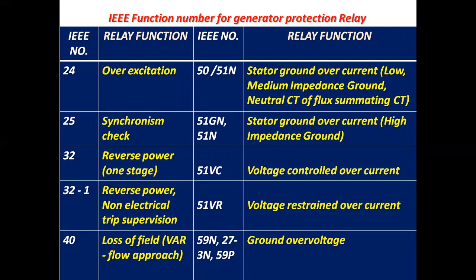IEEE function number for generator protection relay. IEEE number 24 is overexcitation, 25 synchronism check, 32 that is reverse power single stage, 32-1 reverse power and non-electrical trip supervision relay, 40 loss of field that is due to mho approach.